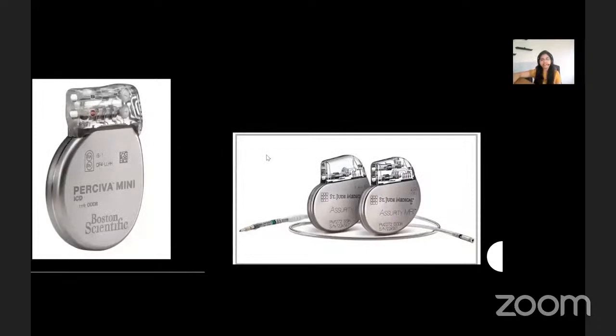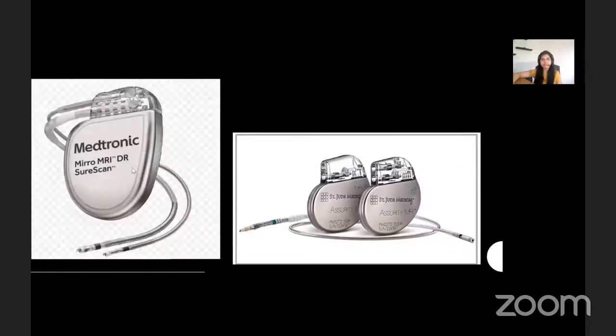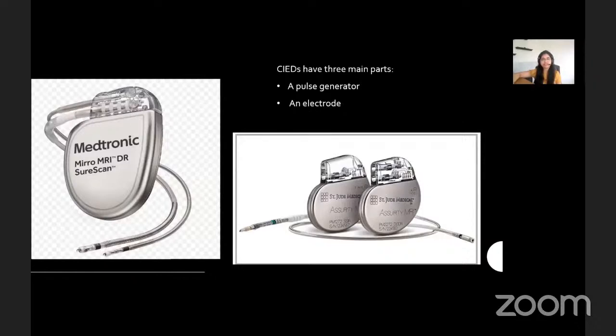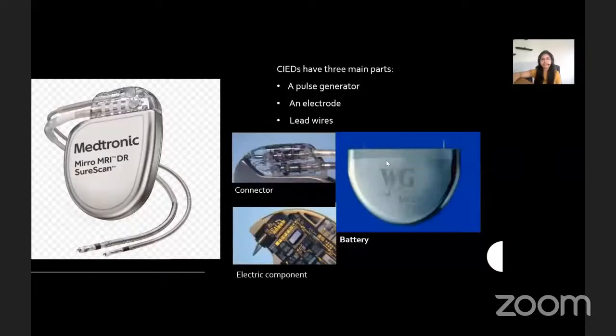Many vendors supply a variety of devices — such as St. Jude Medical, Boston Scientific, Medtronic, etc. — but the basic parts of a device remain the same. An implanted device has a pulse generator with a finite battery, electrodes connected to the generator via a terminal connector pin which should be engaged, and the distal end of the electrode is composed of lead wires with different tips for attachment to the heart. The image shows the battery, the connector pin, and the internal electrical circuitry of the device generator.